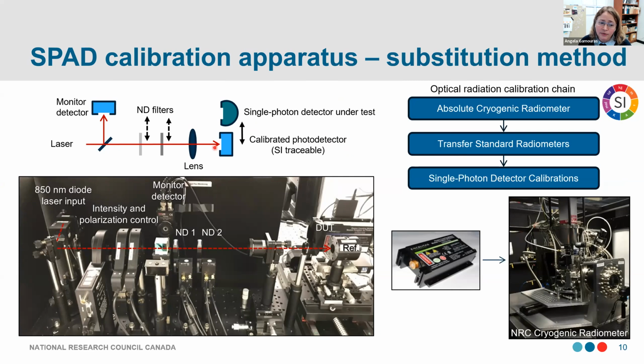This detector, calibrated traceable to the SI system of units, our transfer standard detector, has been calibrated in the microwatt range. We need to reduce the optical power down to a femtowatt range for our single photon detector. So we use two neutral density filters. First we measure our light on our reference standard detector with one ND filter. Then we put both filters in the optical path, move our translation stage over, and measure our signal on our detector under test, our SPAD.